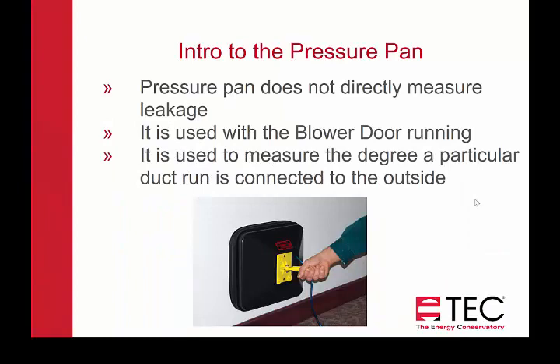An important thing to understand is that pressure pans do not measure leakage. What we're going to be talking about today is primarily using it to diagnose duct leakage, although it is often used to do zone pressure diagnostics. A better application: recessed lights are a typical thing that they're used for, to try to determine a pass/fail — but a pressure pan is not the right device for that. You could use an exhaust fan flow meter, for example, with a minimum rating of 10 CFM using the smallest opening.